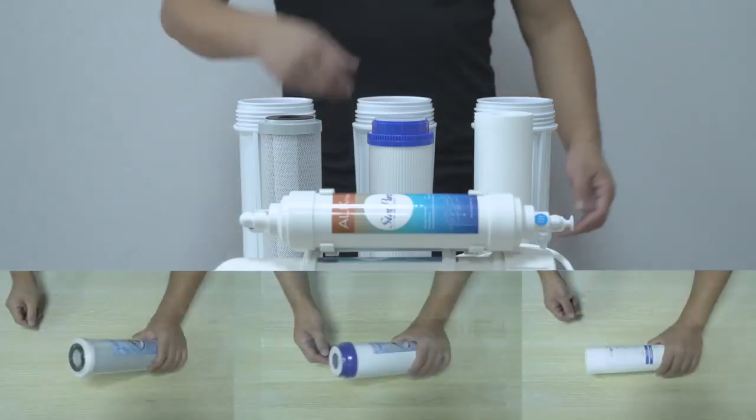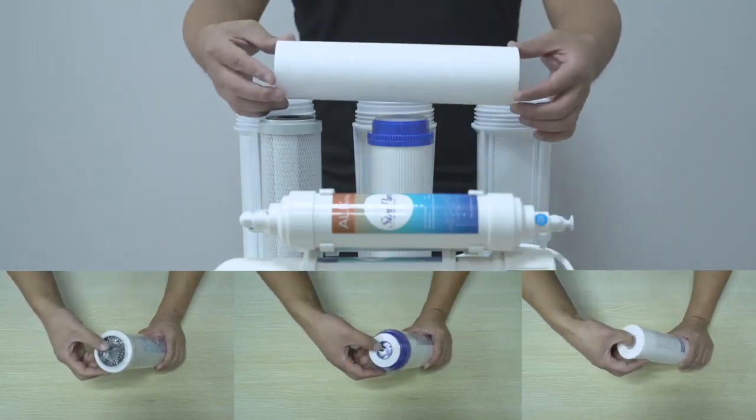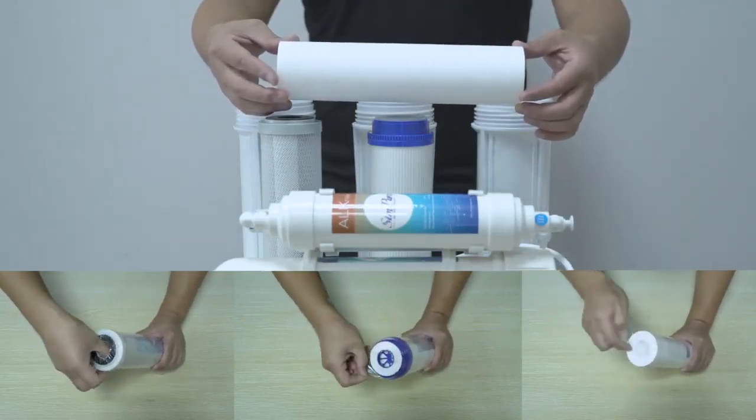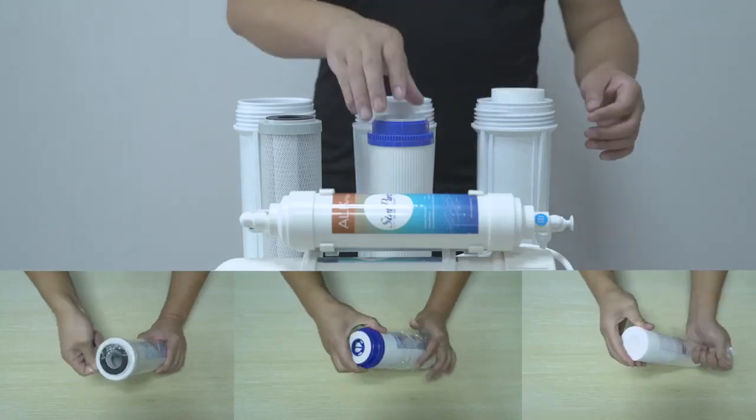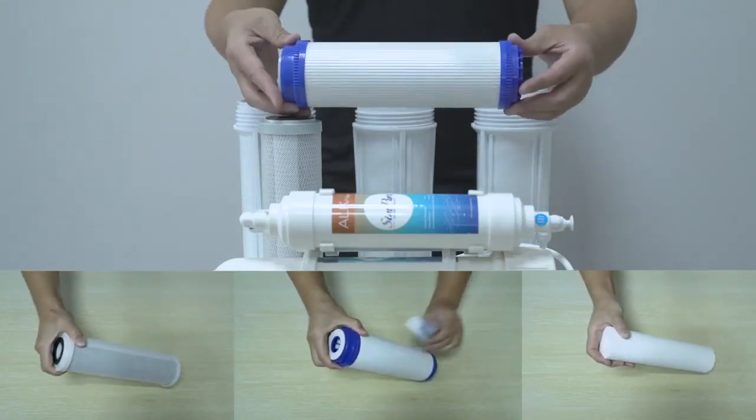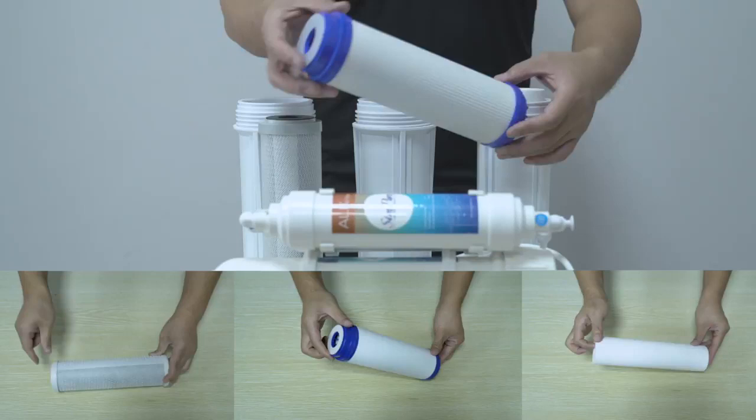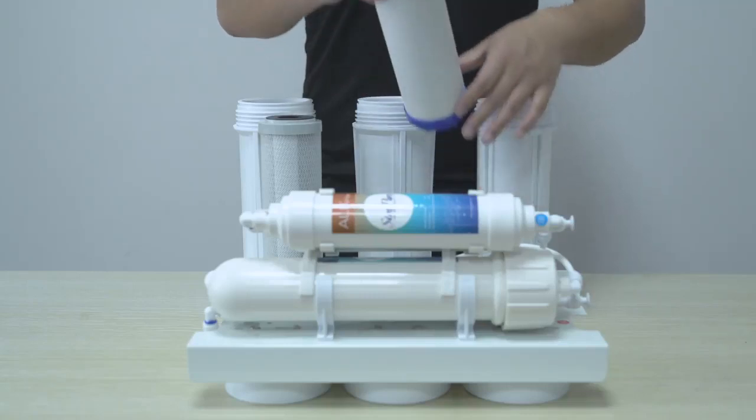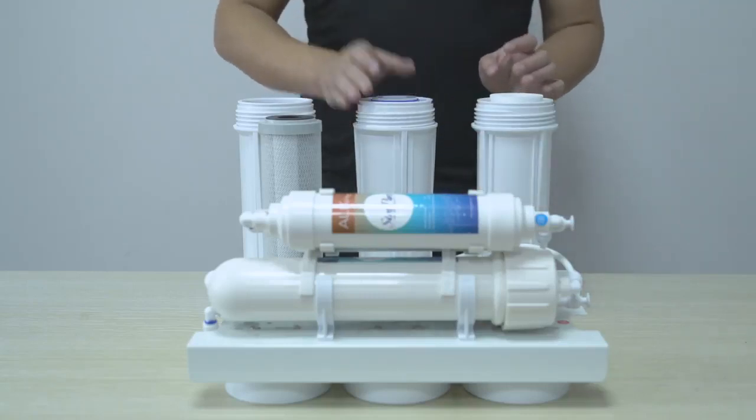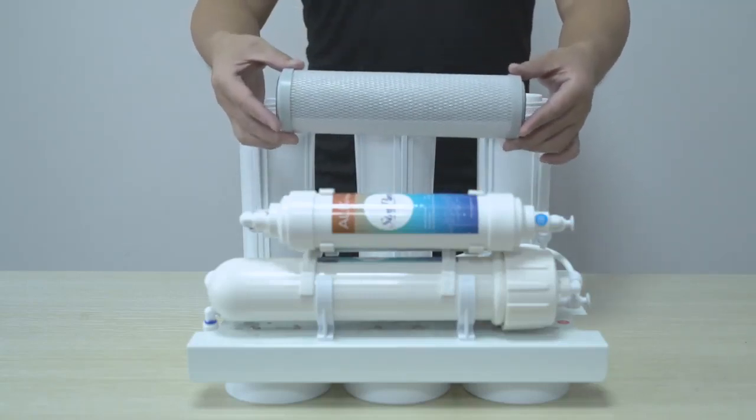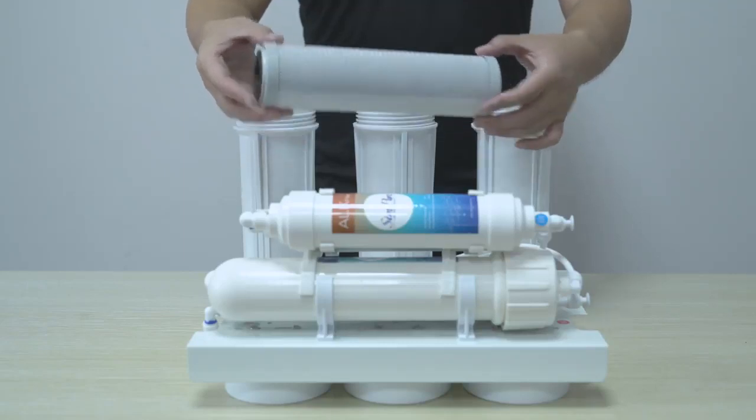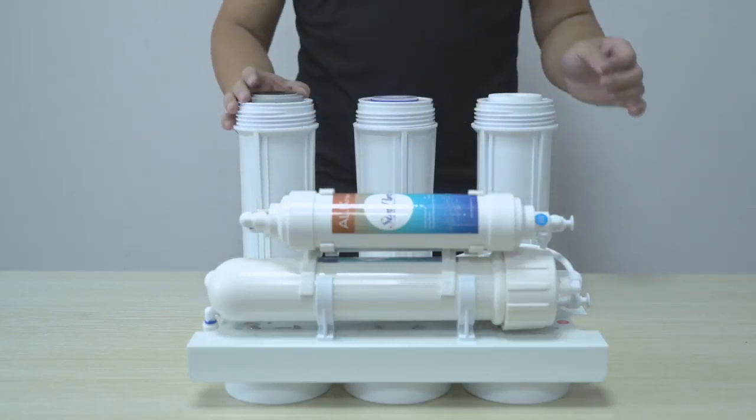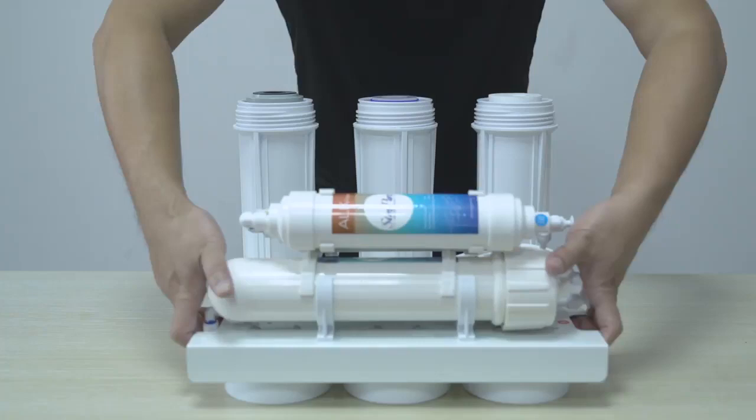Filter cartridges: Install the PP filter in the left-hand filter bowl either way around after removing all the packaging. Next, be very careful when installing the GAC filter into the center position bowl that is the correct way around and all packaging is removed. The sealing gasket must face upwards towards the filter bowl opening. Finally, fit and unpackage the CTO filter either way around into the right filter bowl and hand tighten.